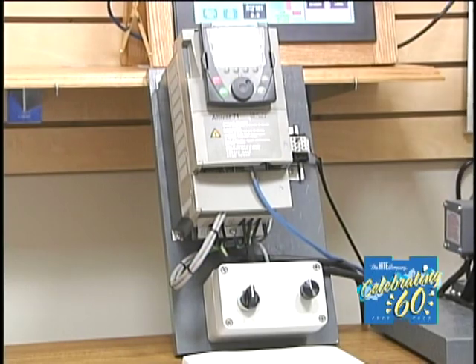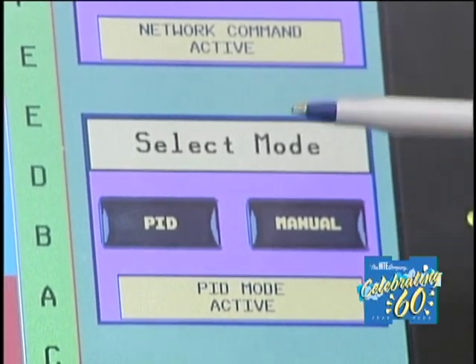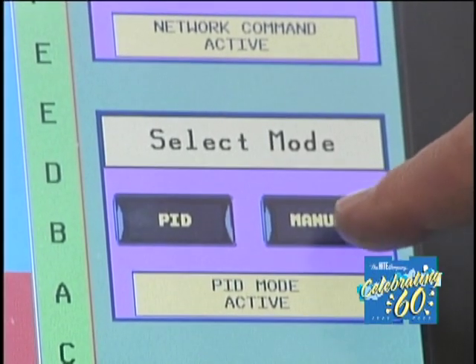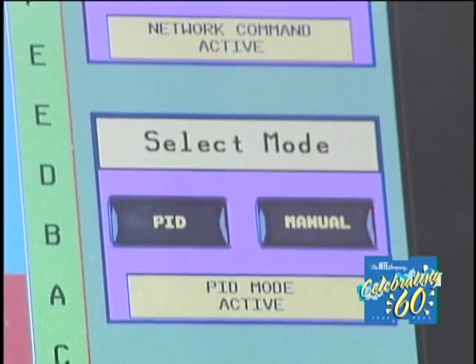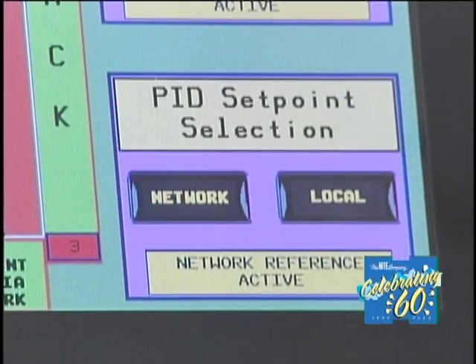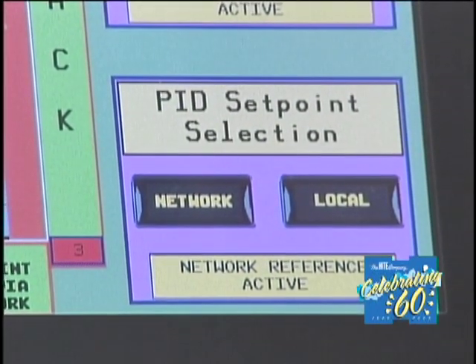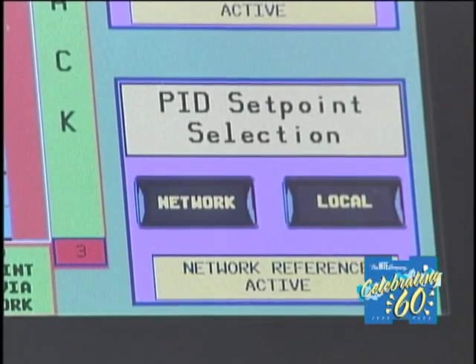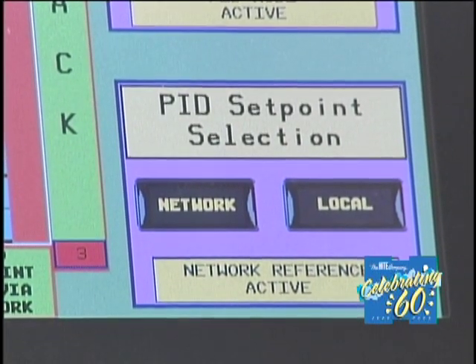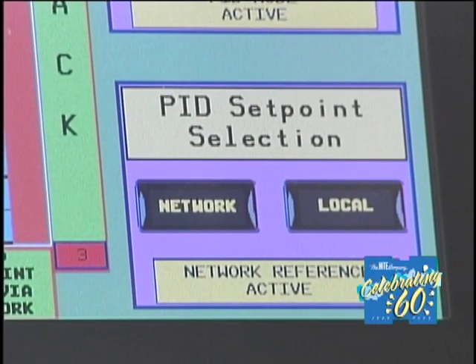We'll start out in network. Our mode is either going to be PID or manual. PID means the PI controller in the drive controls the speed of the motor. If we go into manual, that's direct control of the drive output frequency with the speed pot on the local control box. For PID setpoint, on network we use the bar graph on the touchscreen. If we hit local, the speed pot on the local box becomes our setpoint — it sets the setpoint and then the drive controls the motor speed to maintain the bottle in the tube.